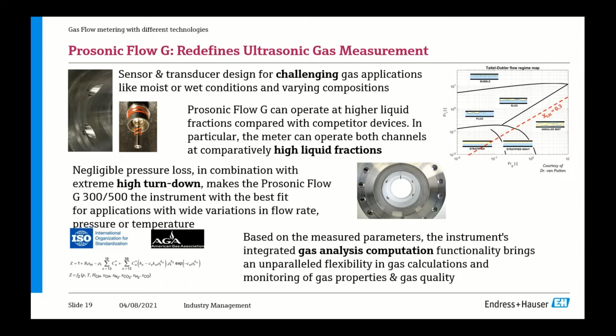We have this gas analysis computation functionality. We call it advanced gas analysis. That is a calculation package we have embedded in the software, which gives you really an unparalleled flexibility in gas calculations and the monitoring of the gas properties and the gas quality. Complicated formulas like you see on the left-hand side, the ISO 12213 or the AGA NX19, are all embedded in the instrument, and they just make your life easier to use these standardized calculations. Next slide, please.